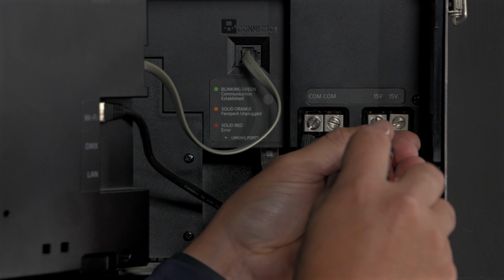Next, we're going to review cloud mode and how to verify that the controller is properly connected to cloud services. Go to Setup, then Wi-Fi. Make sure that you're still connected to the router. For the network to operate, make sure that the network has internet access and access to AWS on the controller. The best way to make sure that this is connected is to go to Test. It'll run through a series of tests. As long as everything says OK, especially checking AWS, then this controller is ready to be connected to the cloud. Press Done. Reasons the controller may not connect to AWS can include router settings, security restrictions, or incorrect ports.